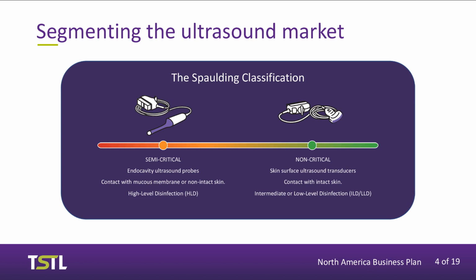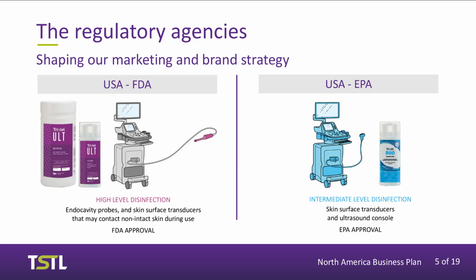This is very relevant to the way that we build the business out and our regulatory strategy that we've pursued. So moving to the next slide, you can see how the two regulatory bodies in the United States have shaped our approach to the marketplace. The FDA has jurisdiction over high-level disinfectants. The EPA, the Environmental Protection Agency, has jurisdiction over intermediate and low-level disinfection. And so we've had to create for the United States market two products. We are in the unbelievably strong position competitively to be able to present to the market both an HLD and an ILD, thereby presenting a solution for every one of the ultrasound probes and transducers that are used throughout the country.